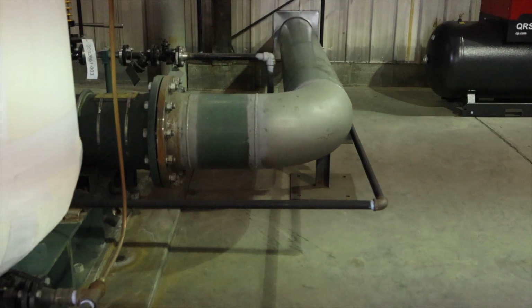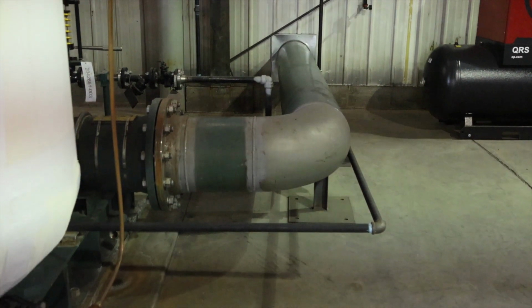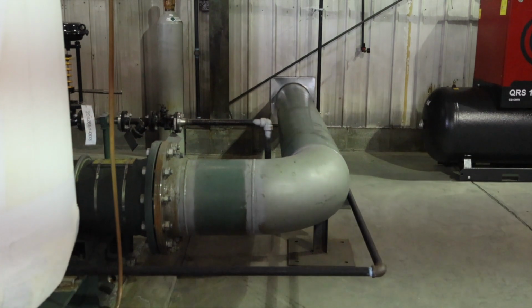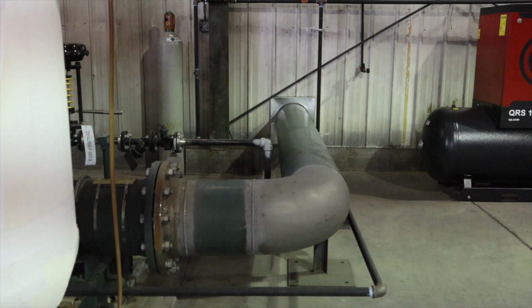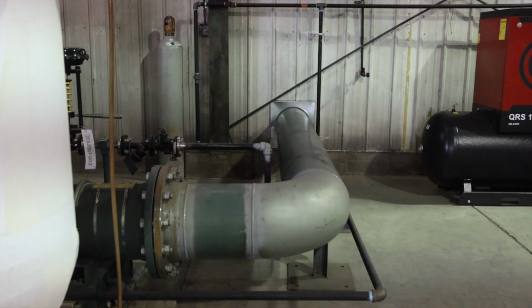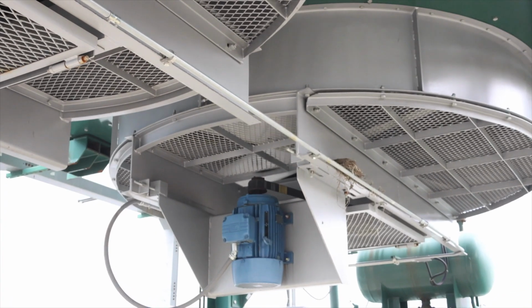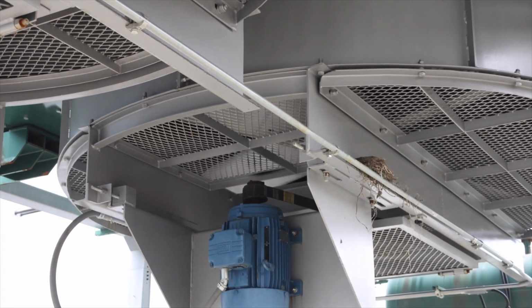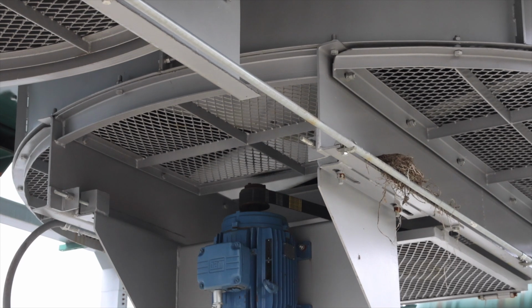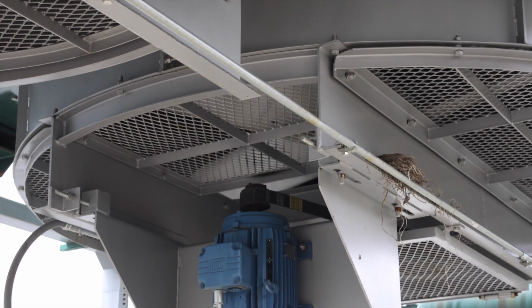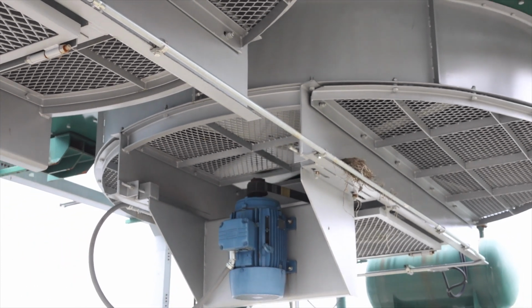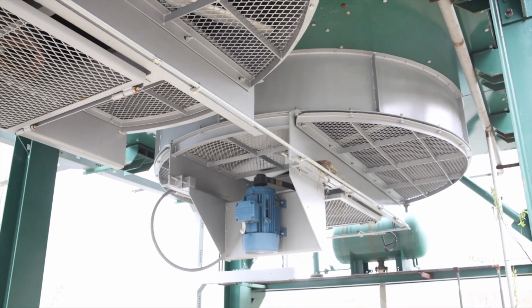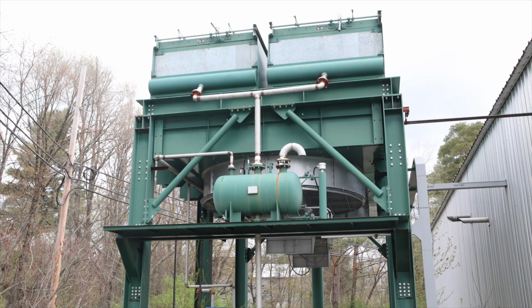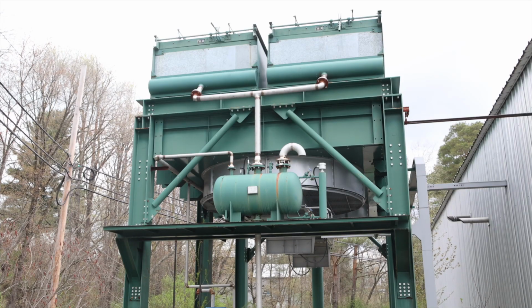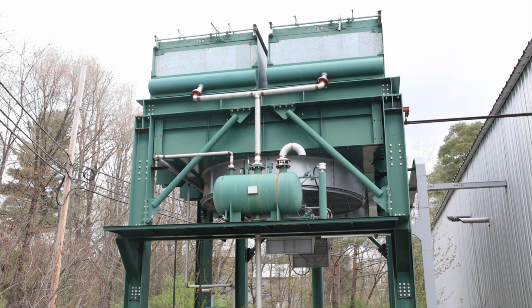After the steam has been used to make the power in the screw expander, it exits the expander at a much lower pressure and needs to be condensed back into water form. The low-pressure steam is transported by piping to the air-cooled condensers. At the condensers, large fans force ambient air across fin and tube radiators to cool the steam, forcing it back to water form. The condensate water is gathered in the condensate tank, which is monitored to maintain a consistent level.